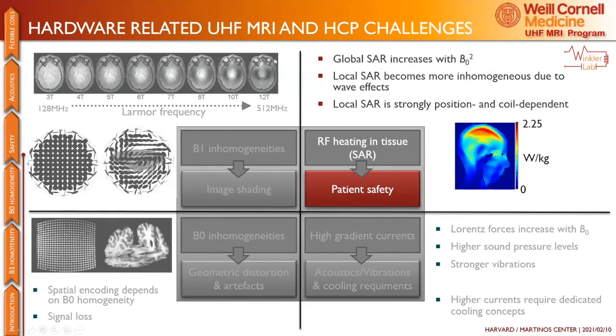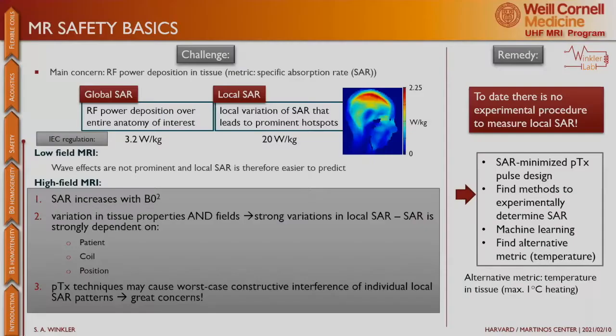So I'll explain in more detail in the next slide. The challenge here is that you have RF power from this RF B1 signal deposited in tissue. This is measured most commonly as the specific absorption rate. The reason this is a concern is because what that does is heat up the tissue, right? If you make a very brute comparison, that's the same thing as a microwave oven. That's what a microwave oven does, just at much, much higher powers. And so you don't want that, right? You don't want to damage or cook any tissue.